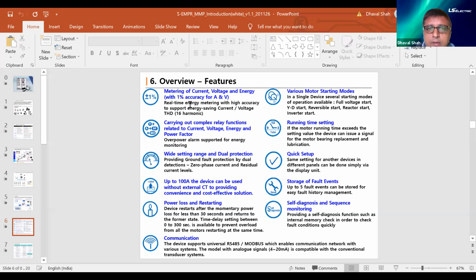So what are the overview features? Metering of current, voltage, and frequency with 1% accuracy for current and voltage, and you get harmonic measurement up to the 16th harmonic level. Carrying out complex relay functions related to current, voltage, energy, and power factor. Wide range available, as I mentioned, 5 to 100 ampere. In fact, this relay is available from 0.3 also, but then the higher side would be 0.3 to 30 ampere or 0.3 to 60 ampere. So basically the range is available from 0.3 ampere to 100 ampere. Again, as we mentioned earlier, you save on CT and you save on compactness of the panel, so everywhere there is a cost reduction.